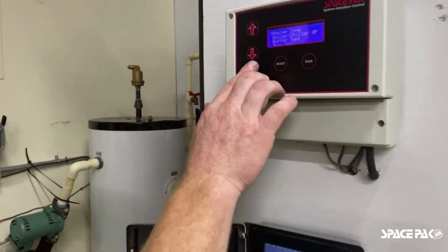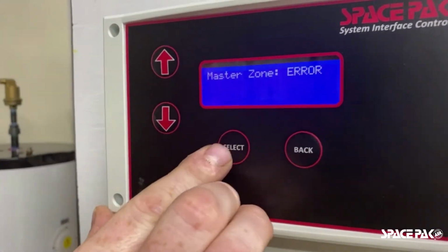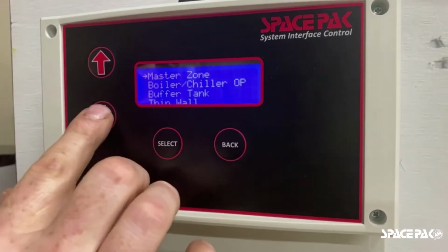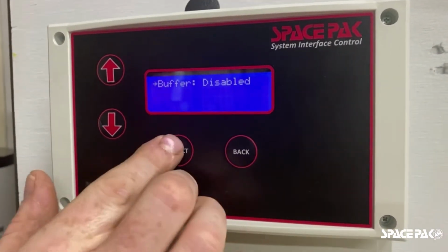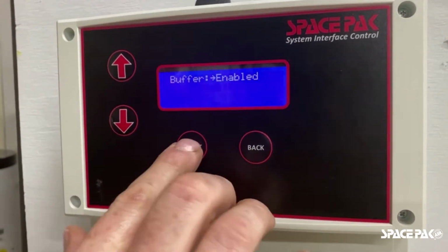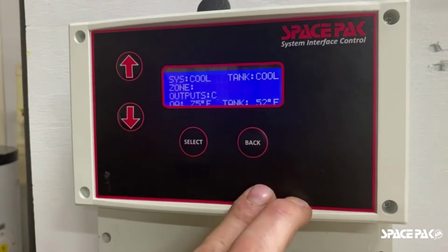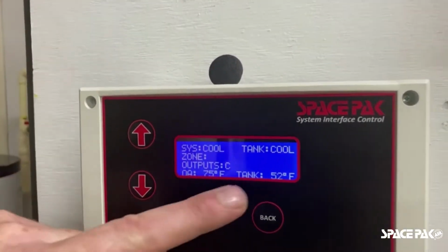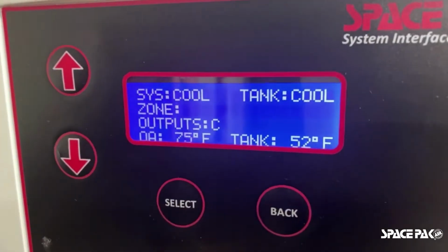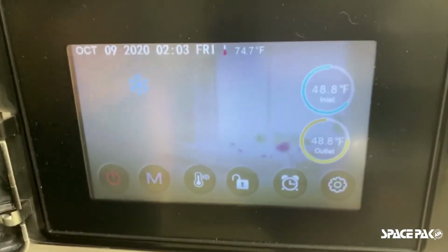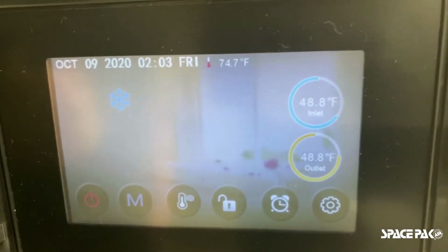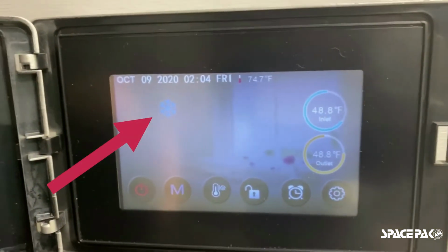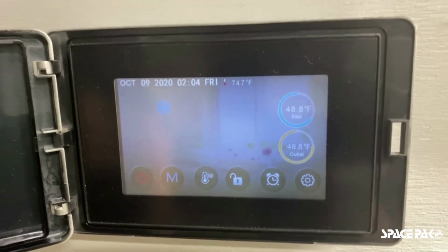So we're going to go through a couple of items here. Master zone, there's an error because we haven't chosen what a master zone is. We're going to go to buffer tank, select again, enable our buffer tank, select again, and then back out. Now our system is going to be cooling. Our tank is going to be looking for a cool temperature. Now if we bring our attention back down to the lower control, you can see that the screen has in turn changed color, and we can see a nice brightly lit blue snowflake there in the unit. That's telling us that we have a cooling call being applied currently.